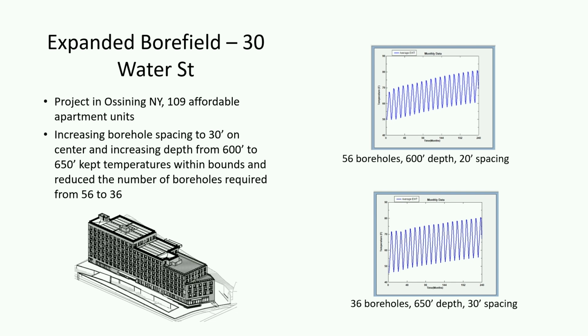So we run another iteration. We actually reduce the number of boreholes. We spread them out a little further. We go from 20 foot on center to 30 foot on center. We drill them 50 feet deeper, and we see a flatter curve. We don't see that runaway increase in temperature, and it's a more sustainable system.